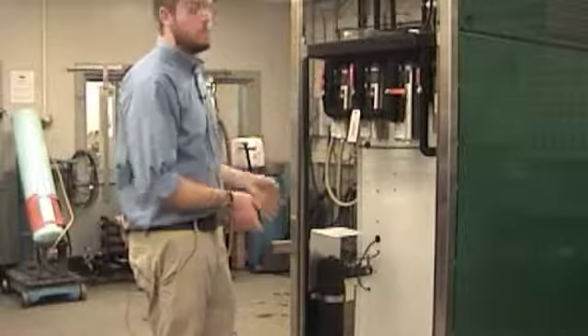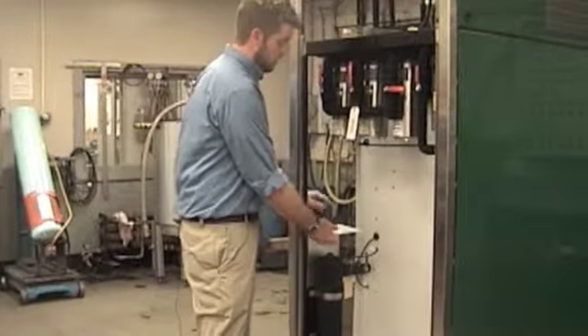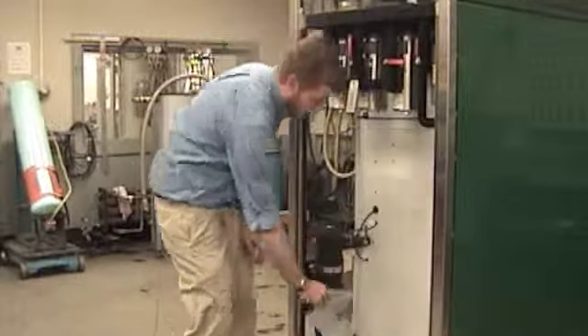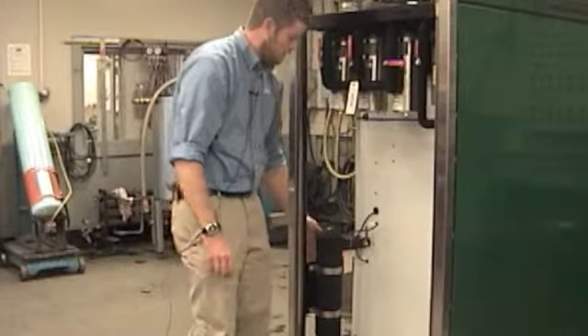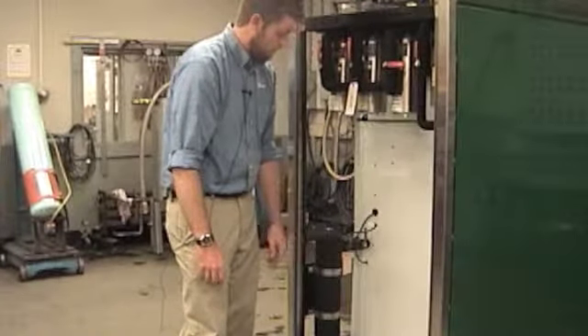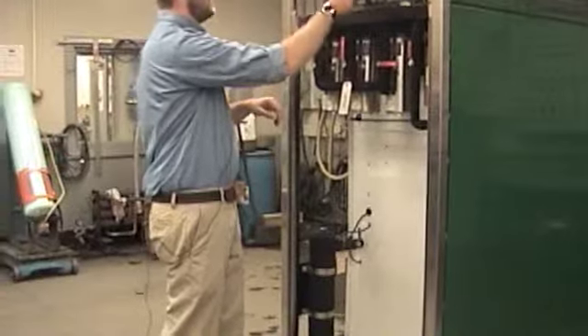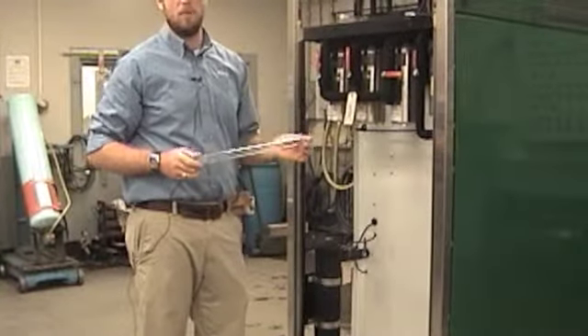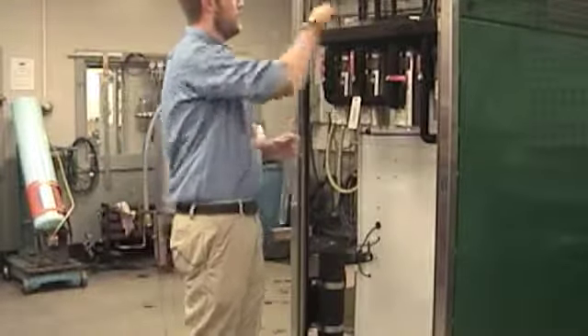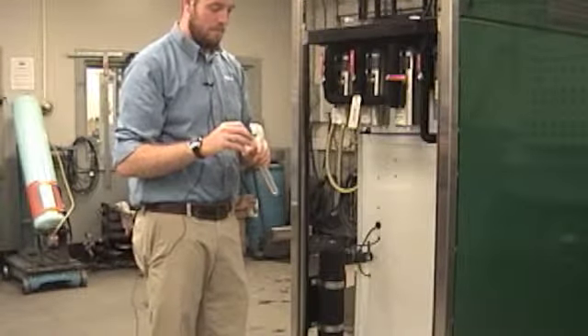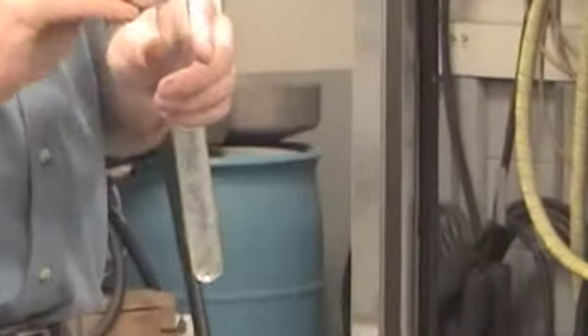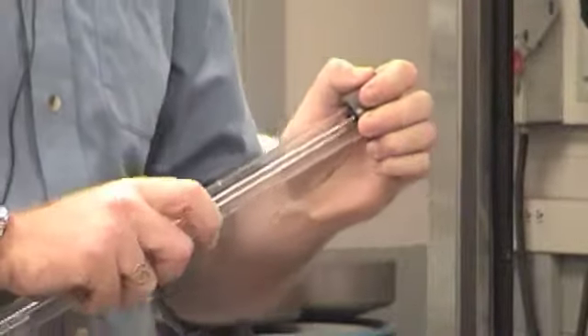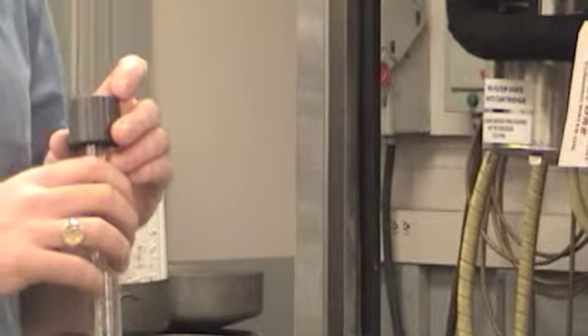So to install the UV bulb into the UV sterilizer, you're going to want to be sure to first remove this protective guard here. You may have to take a nut driver and loosen up slightly the bolts here, but not all the way. And then your components, you'll have a quartz sleeve, which you'll find in a cardboard box in your annual maintenance kit. This O-ring, and the trick to this is to just put the O-ring on the very lip of the quartz sleeve, and then using the cap here, sort of roll it down into place, and that'll create a nice seal, keeping the water out of the quartz sleeve.